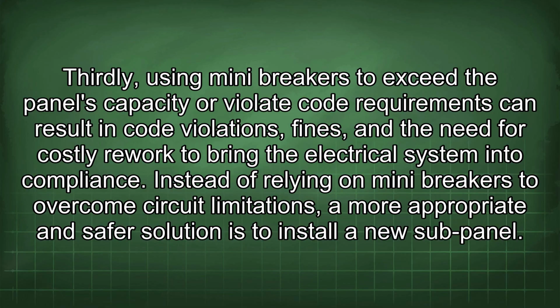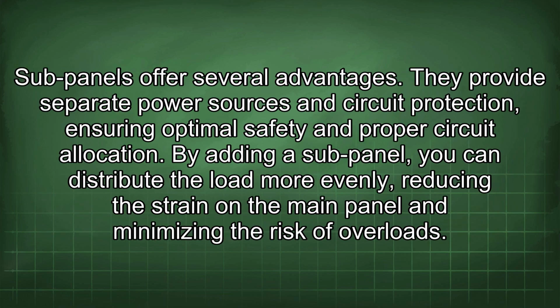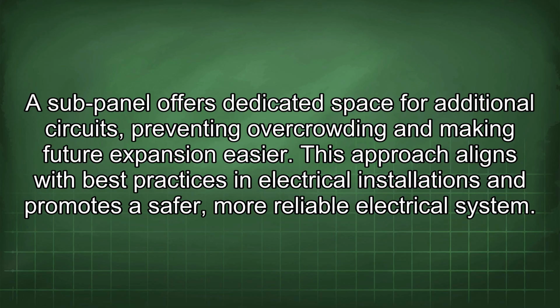Instead of relying on mini breakers to overcome circuit limitations, a more appropriate and safer solution is to install a new sub-panel. Sub-panels offer several advantages. They provide separate power sources and circuit protection, ensuring optimal safety and proper circuit allocation. By adding a sub-panel, you can distribute the load more evenly, reducing the strain on the main panel and minimizing the risk of overloads. A sub-panel offers dedicated space for additional circuits, preventing overcrowding and making future expansion easier. This approach aligns with best practices in electrical installations and promotes a safer, more reliable electrical system.